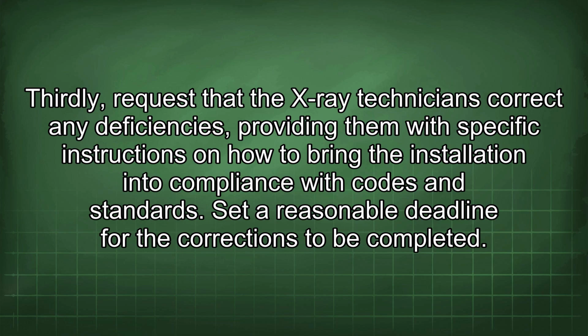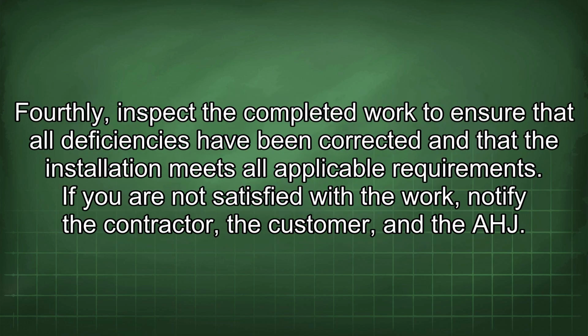Thirdly, request that the X-ray technicians correct any deficiencies, providing them with specific instructions on how to bring the installation into compliance with codes and standards. Set a reasonable deadline for the corrections to be completed. Fourthly, inspect the completed work to ensure that all deficiencies have been corrected and that the installation meets all applicable requirements. If you are not satisfied with the work, notify the contractor, the customer, and the AHJ.